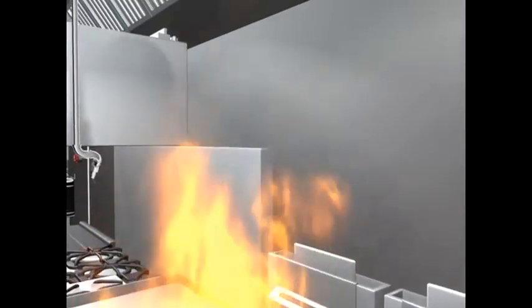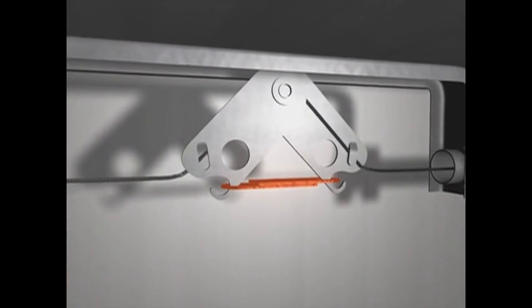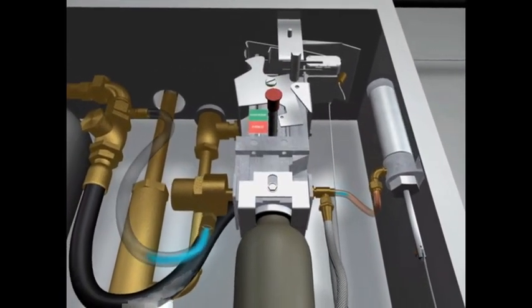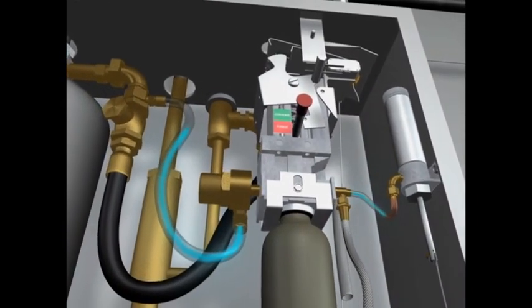Detecting a fire, a Piranha fusible link responds to the rising temperature and separates, triggering the release of a compressed gas cylinder within the Ansul Automan release mechanism.